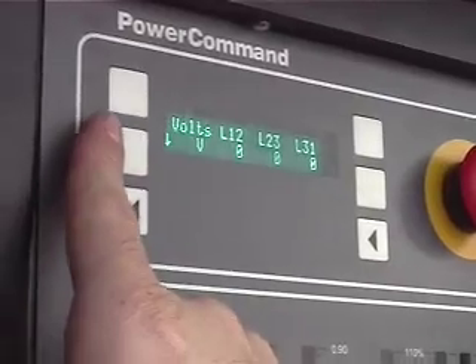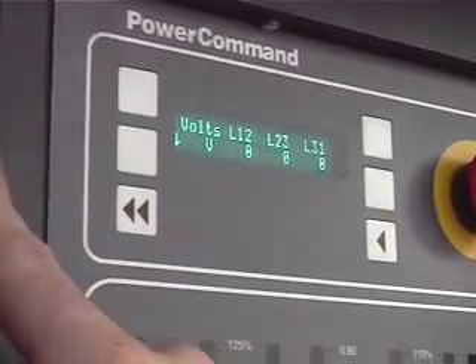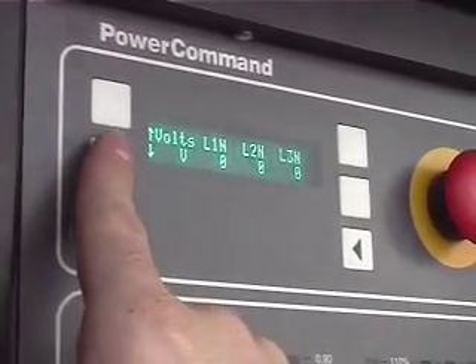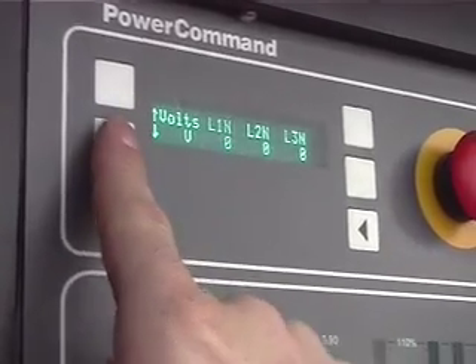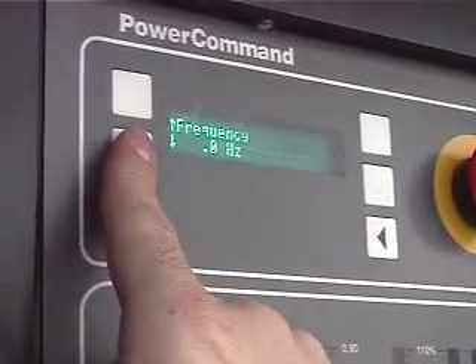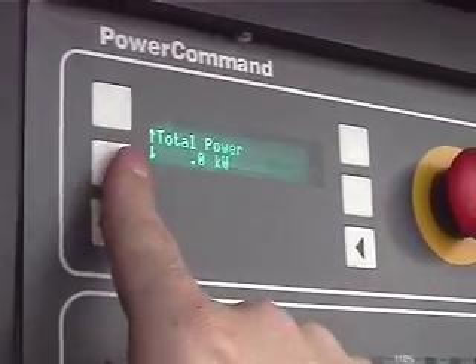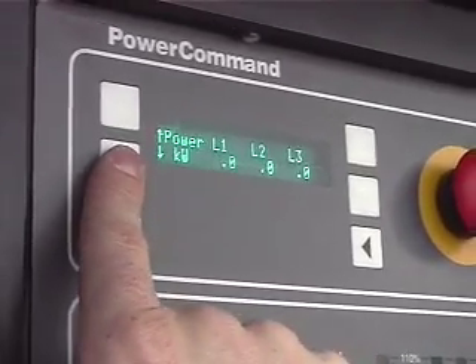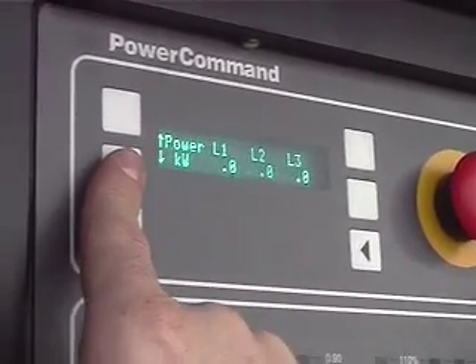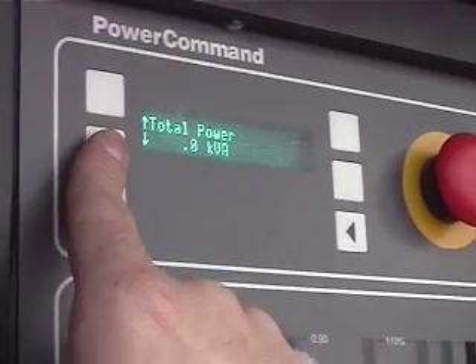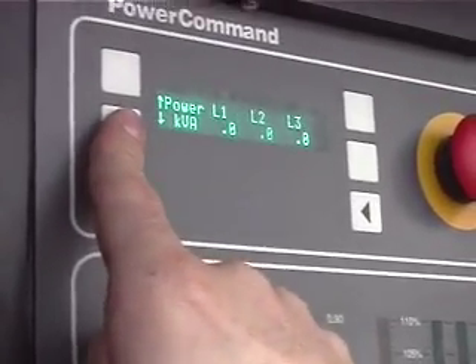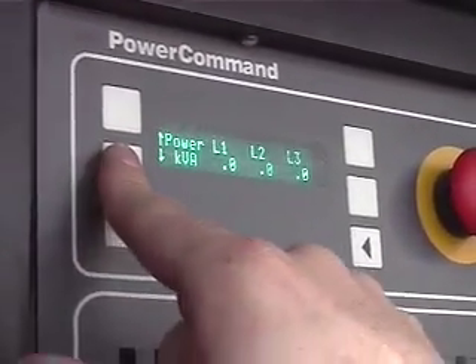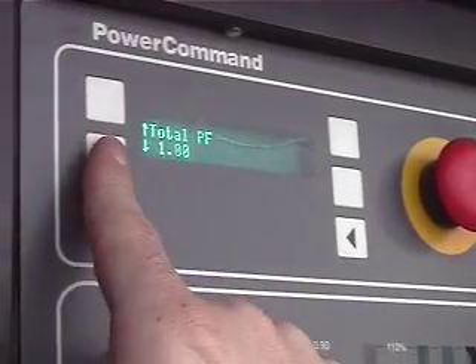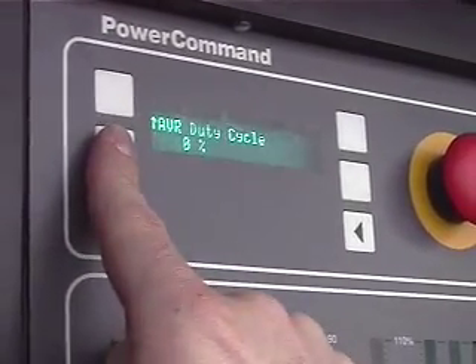Alternator, that's just your generator end. That's where all your voltages are going to be: line-to-line voltages as well as line-to-neutral voltages. The current, frequency, total kilowatt power, kilowatts per phase. Make sure the electrical engineer divided the loads up right. Then kVA per phase, power factor, and power factor per phase.